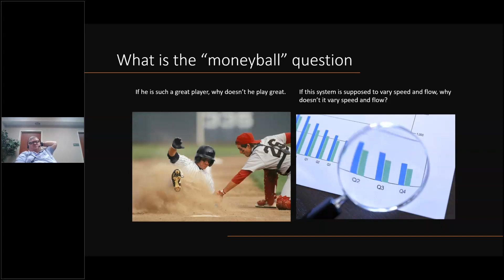Check the operation of the system through the building automation system. Look for contradictions of operation again. Has the system ever worked correctly? Can somebody prove that? That's where the TAB and commissioning reports are gold in identifying problems from the outset. If I hadn't read that TAB report on that project, and nobody else did, I wouldn't know. The building was still being finished when I read that. Nobody would know that was a problem.